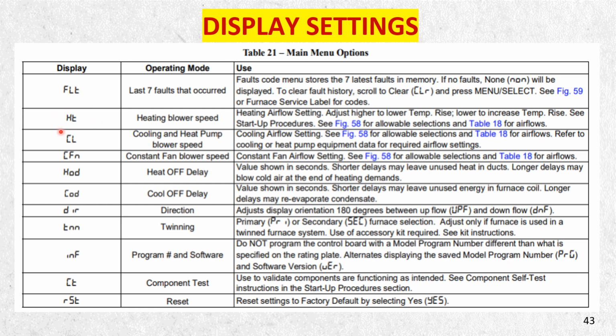And then you go into the HT, which is your heating blower speed. And like I said, it'll show you what number it is. You click the right button on the display to change that manually, or we'll show you how you hook it up with your phone. So these are your numbers here. You've got the heat off delay, like we talked about. You can change that. The cooling off delay. What direction: if you're 180 degrees, you're upflow or downflow. And if it's twinning together, is it the primary or the secondary? And then right here, you'll have the info, which is the program number and the software version.